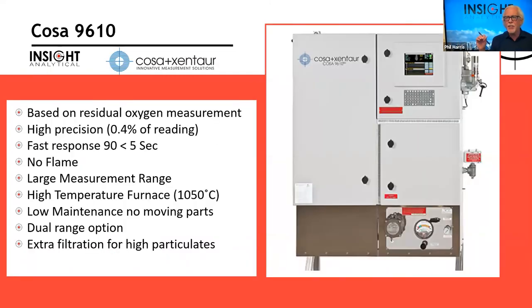So one of the methods of doing it, and the one we're going to talk about today, is the COSA 9610. It's based on this residual oxygen measurement. We're going to talk about how this residual oxygen measurement works. Properly calibrated, around the types of fuels you're going to be using, you can get very high precision, typically around 0.4% of readings. So you're going to get quite an accurate number that tells you how much fuel you need for that burner. It should be T90, time to 90% response, which is around 5 seconds. So we can get this really fast measurement. We have to get a sample into it quickly and do the fast measurement, and that allows us to do what we call feed-forward control on the burner.